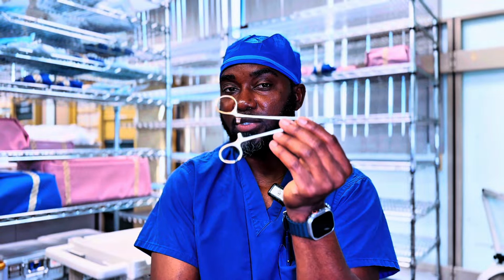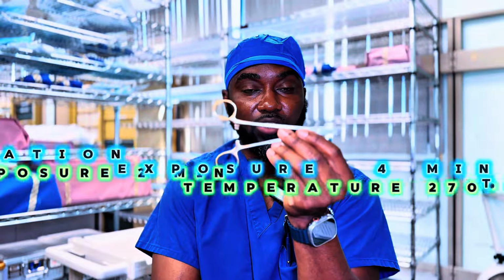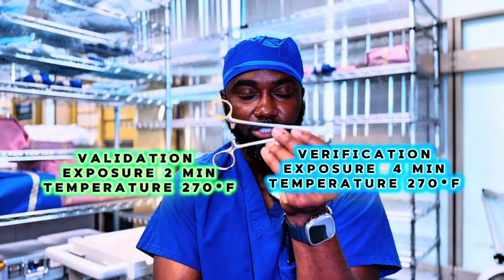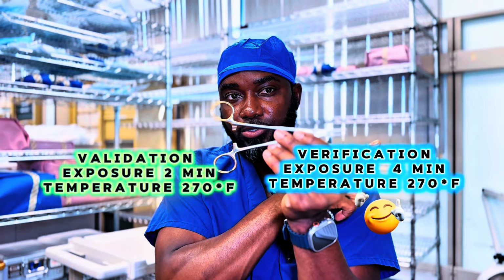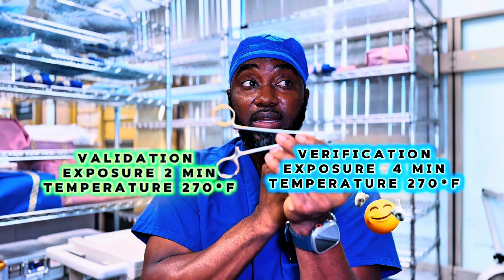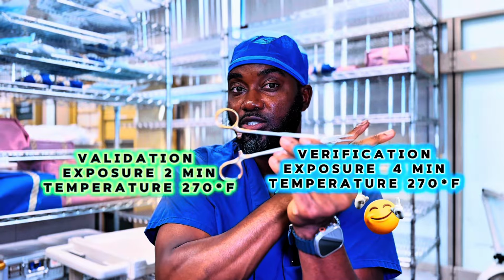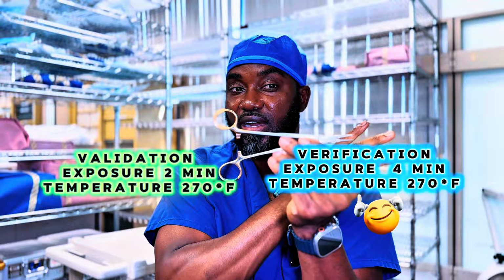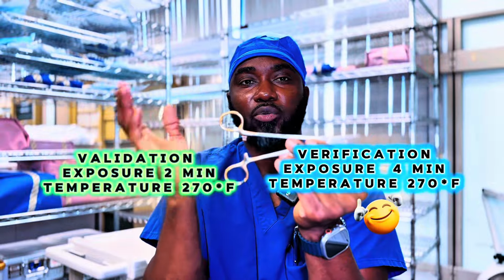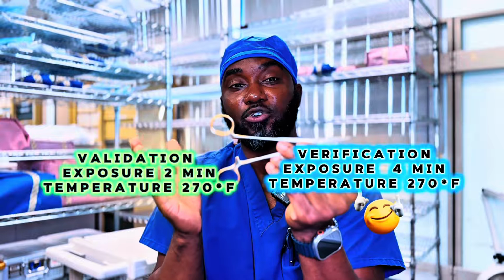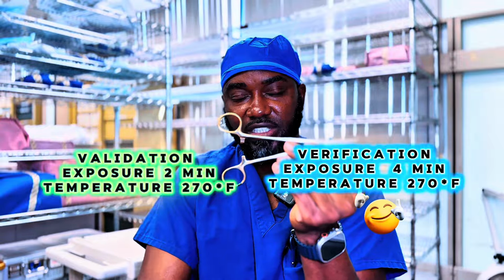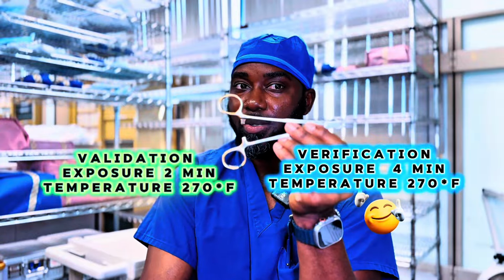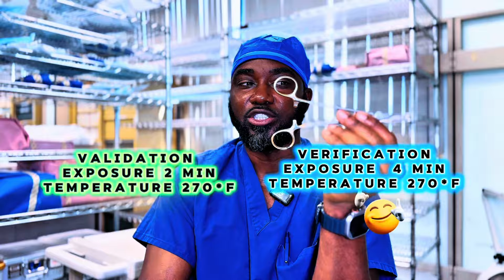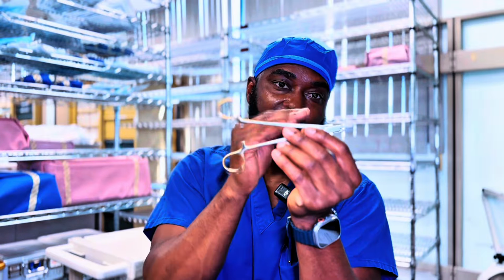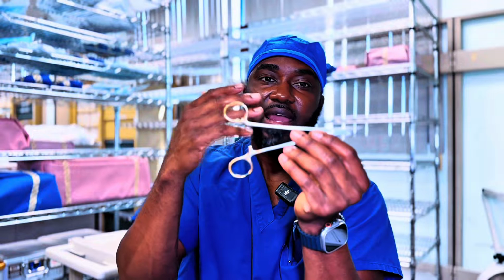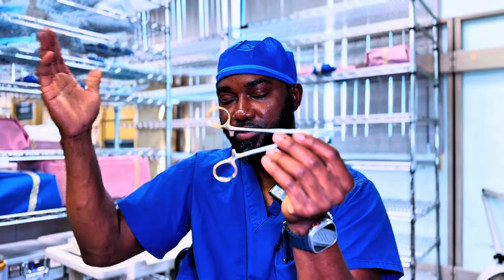When they send this instrument to your facility, there will be written instructions on how to go about sterilizing this instrument, double the time that was used in testing at an independent lab. If the manufacturer tested this instrument at 270 degrees Fahrenheit for 2 minutes in their lab, they will recommend that you test this instrument at 4 minutes exposure at 270 degrees Fahrenheit, but while the instrument is clean. Remember, when they were testing this instrument in the lab, they had to inoculate it with microorganisms to have it dirty, and they will use the same packaging method to send it to you to use.